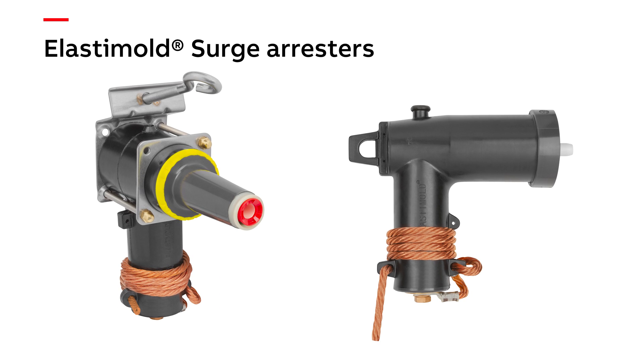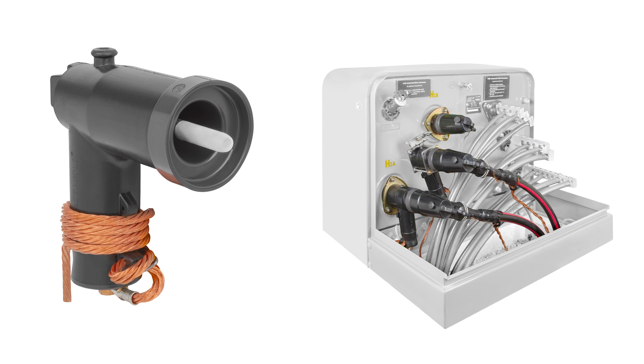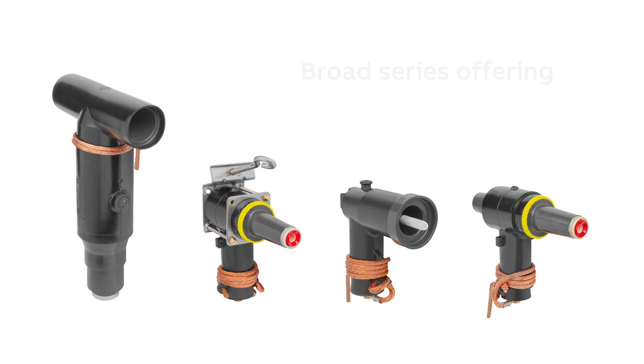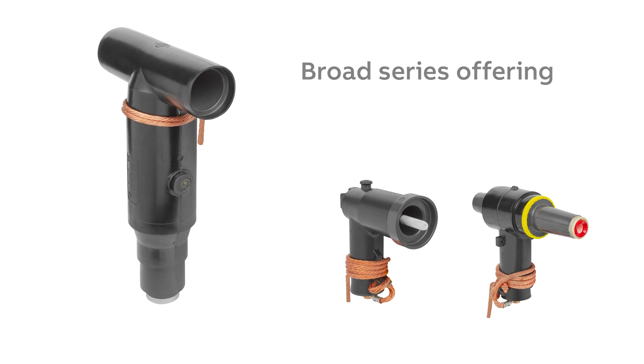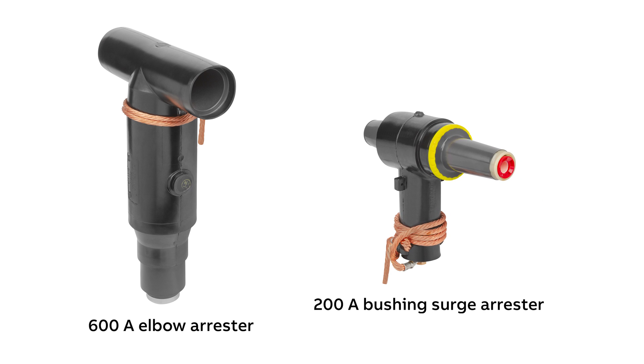Now let's talk surge arresters. Sometimes utility companies that deal mainly with overhead systems aren't aware that surge arresters are needed in their underground systems. They're important from a reliability standpoint for maintaining the integrity of the underground cable insulation and the transformers those cables connect to. Elastimold surge arresters come in configurations that make it easy to provide the best placement for system protection, including a 600-amp T-body arrestor and also a bushing insert arrestor that you won't find anywhere else.